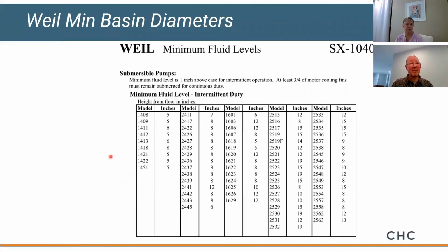Another thing that you might not be aware of: all submersible pumps require some type of minimum fluid level for cooling around the motor itself. That's how the motor gets cooled, dissipating heat into the fluid that's around it. A lot of guys think they're going to drive water all the way to the bottom of the basin. You never want to do that. The pump requires a minimum water level, in this case 12 inches.